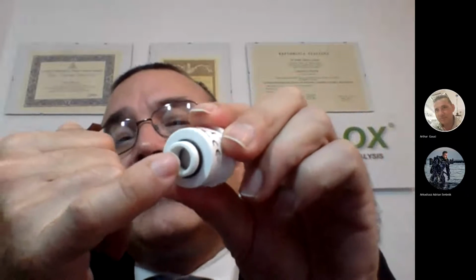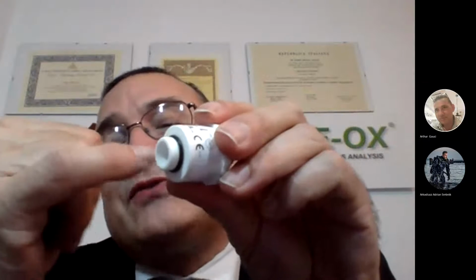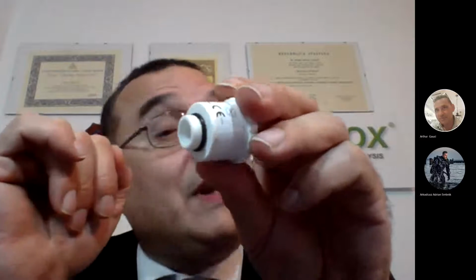Because, as I told you, helium is different. When you have helium in the gas, the sensors, mainly the electrochemical sensors, behave in a different way because of the diffusion of the gas into the membrane of the sensor. The way the carrier gas, that is the inert gas, nitrogen or helium, passes through the membrane is very different if you have helium, and it changes the reading of the sensor. So to avoid this, you have to do the calibration, which is what we are going to talk about today, with a gas containing helium.